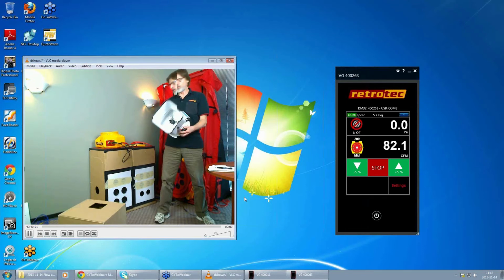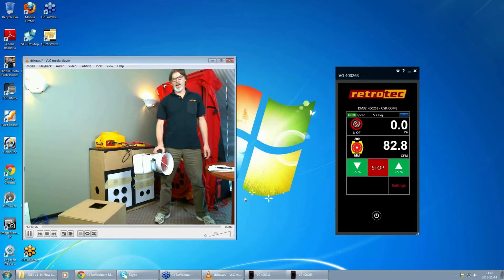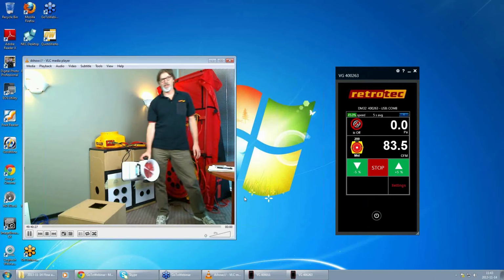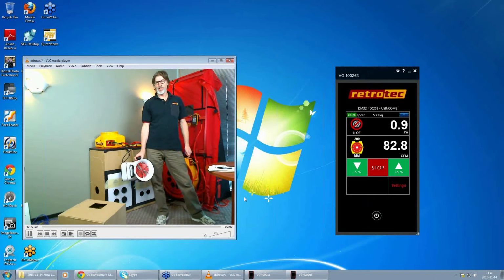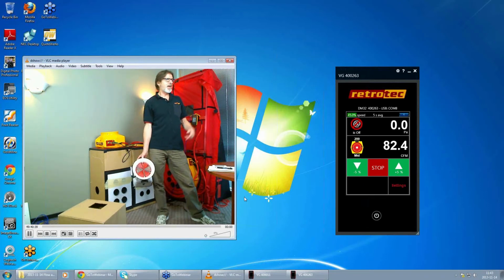One cool thing about it is that if you want to measure supply or return, you just put the device on the same way. It knows the flow direction and will work on supplies or returns, and you don't have to turn the device around or make any adjustments in any way. So it's a very sophisticated unit.